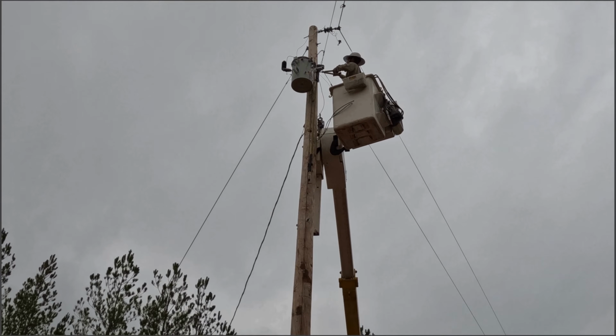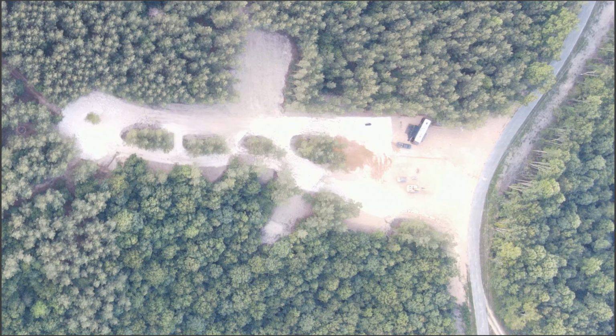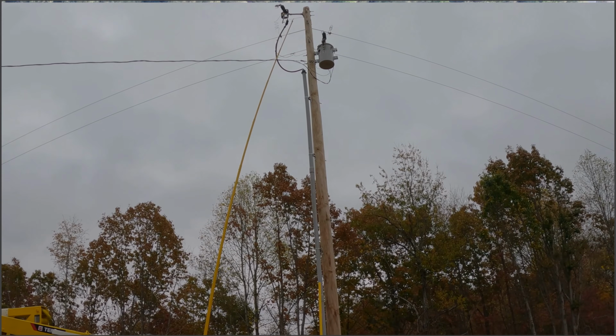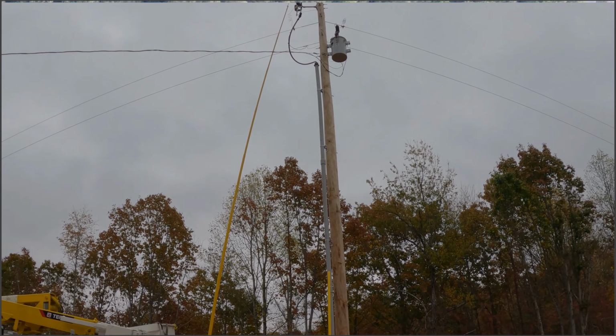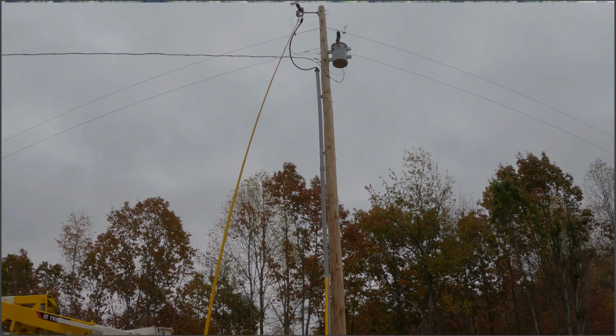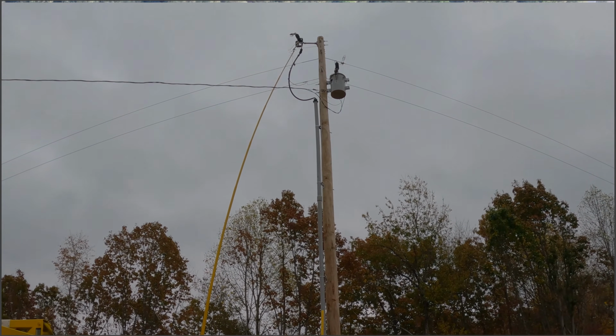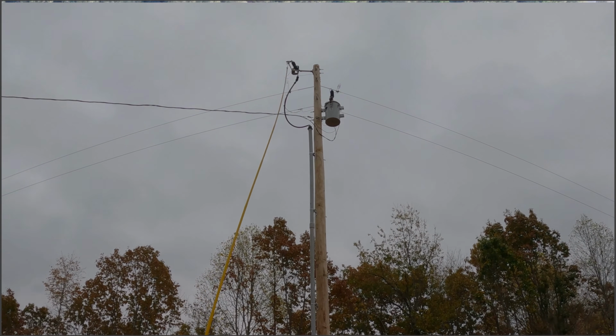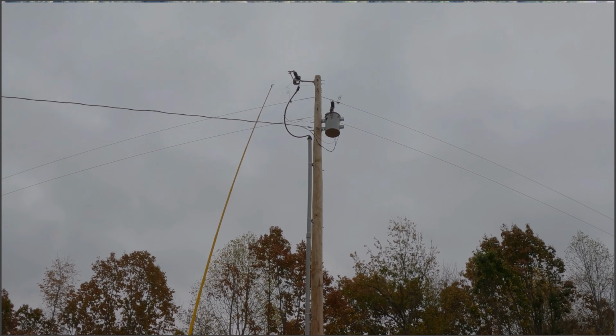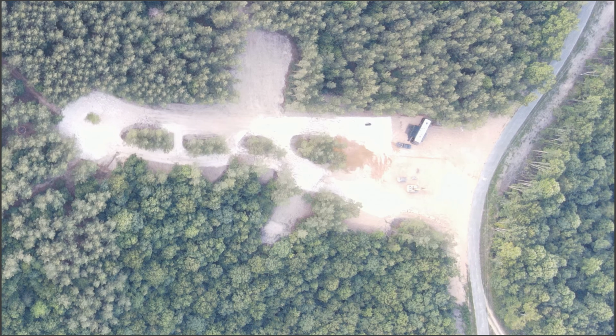So what we have at the road is 14,400 volts of high voltage single phase primary wire running down the road. We're going to connect directly into that primary wire — no transformers, nothing like that, just a direct connect — and run it underground from the pole at the road.